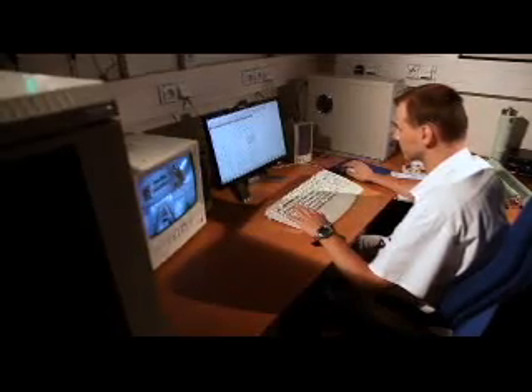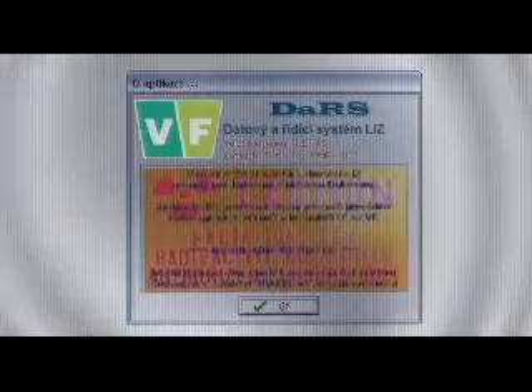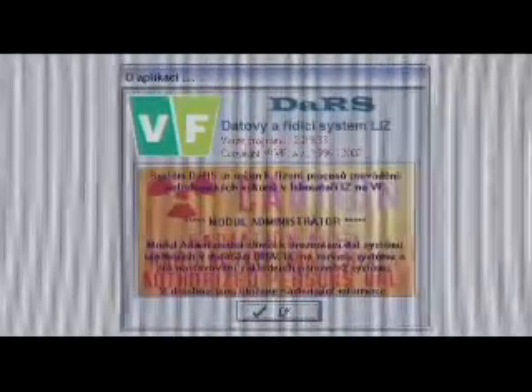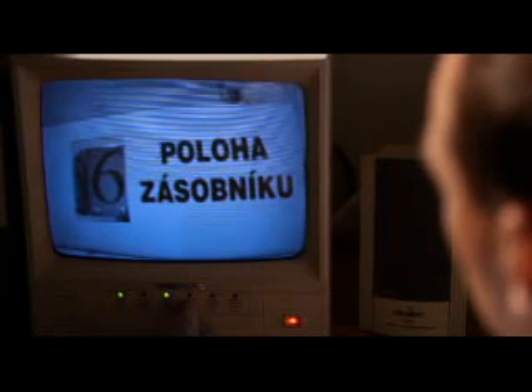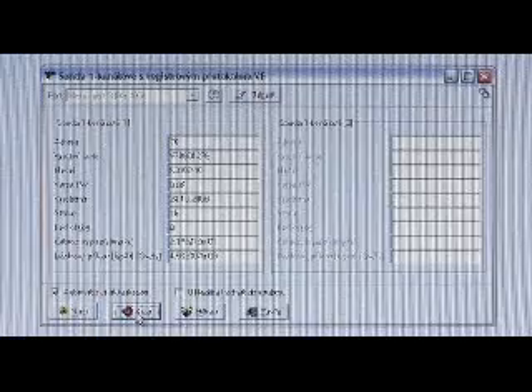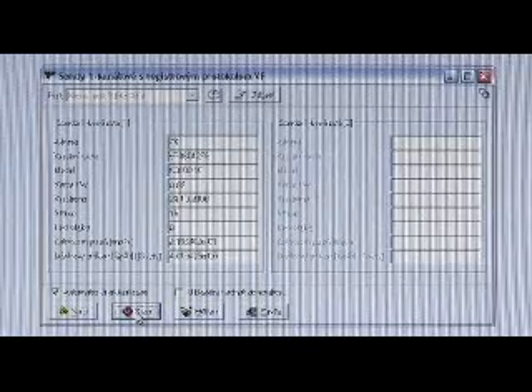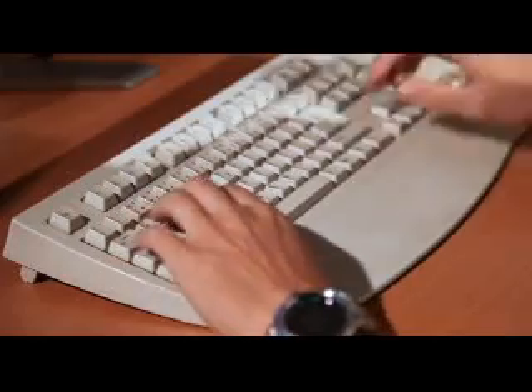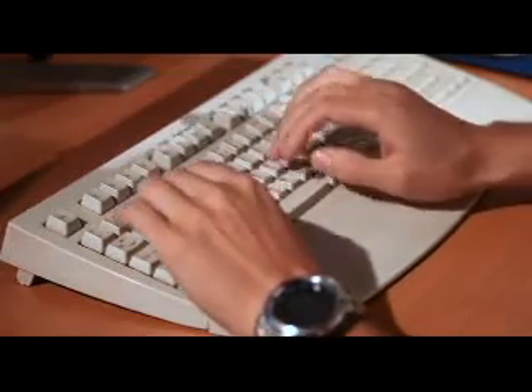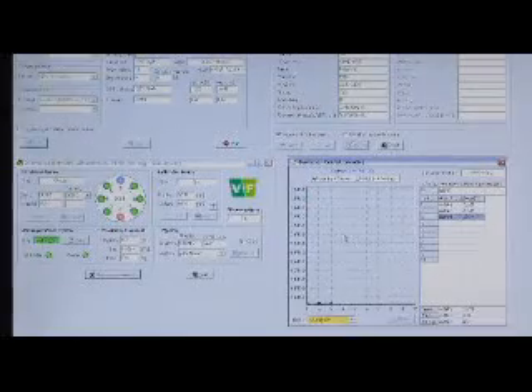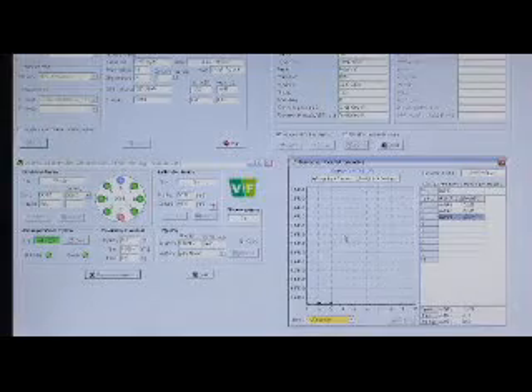After mechanically securing the entry to the irradiation room, the operator switches on the DARS application software. Using this software, the process runs either in automatic mode or is controlled by the operator. In automatic mode, the operator only oversees running operations and the transfer and storage of data into the database. In the case of visual readout, the operator is required to input manually the measured values into the database. This procedure is necessary only when calibrating instruments without a suitable interface.